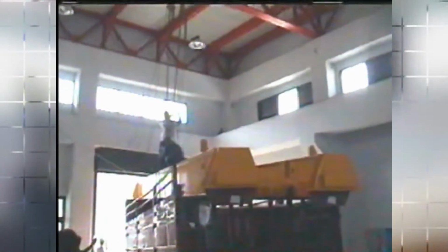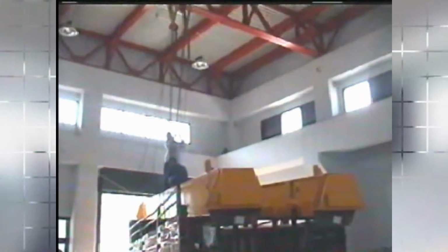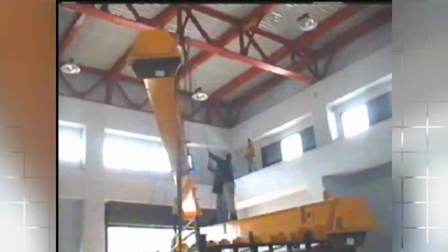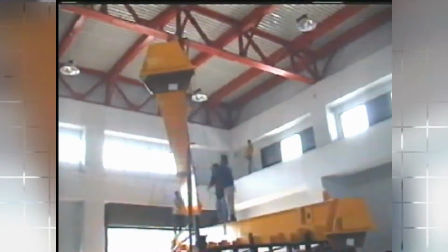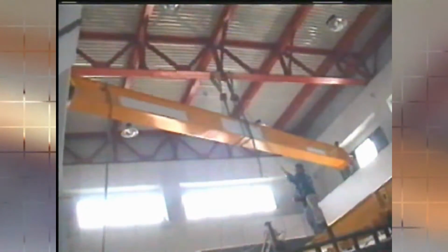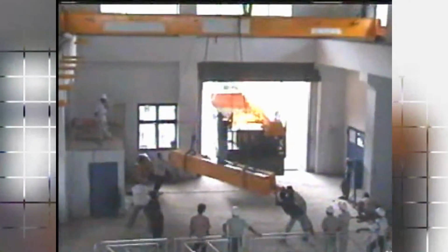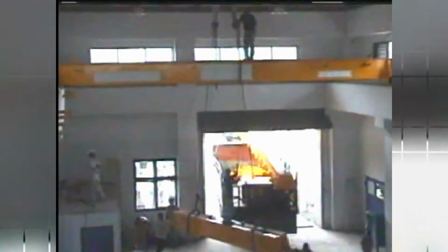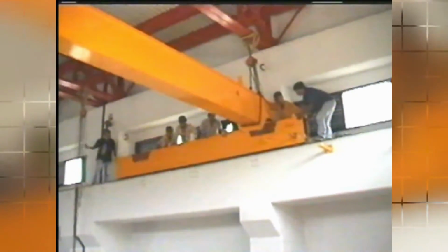The crane provided is a box girder, indoor, traveling type, electrically operated, and provided with one trolley-mounted main hoist and auxiliary hoist. The rated capacity of the main hoist is not less than 5% in excess of that required to enable it to lift the largest and heaviest components to be lifted in the power plant. It is anticipated that the heaviest single lift will be the generator rotor and shaft. It is required that the crane capacity be 25 ton. The main hoist is equipped with a combination lifting eye and sister hook. A 5-ton auxiliary hoist is mounted in the trolley with the main hoist.